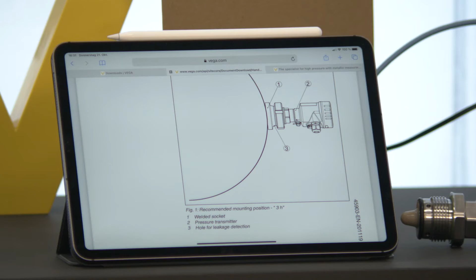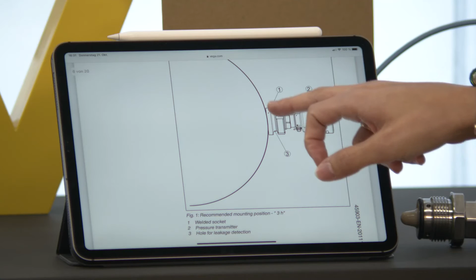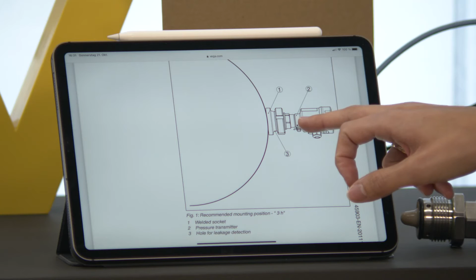But of course, not only the material has to be considered, also the mounting orientation, which has to be planned in the production. For example, here we have the 3A declaration and certificate and the recommended mounting orientation in case there's a leakage inside, and the leakage bore has to be in the correct position to make sure that the liquid drains out and has the possibility here. So this means also during the project planning, the information is available very easily.